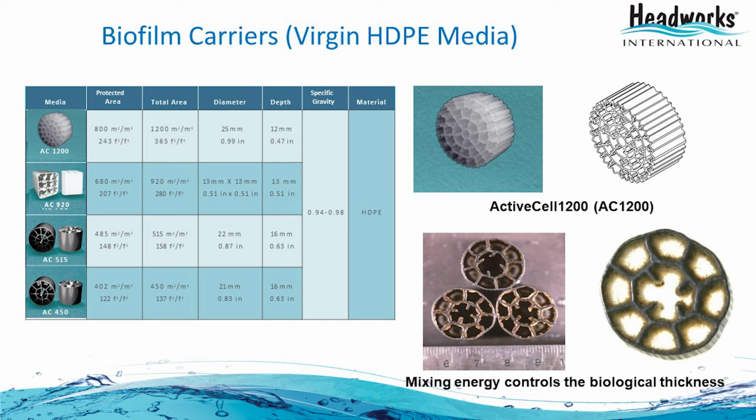It's very easy to mix because it has the same specific gravity as water. For that reason, we don't use any mixing energy. All we need is the air required for oxidation of the materials. That's more than enough to mix the media in the tank.